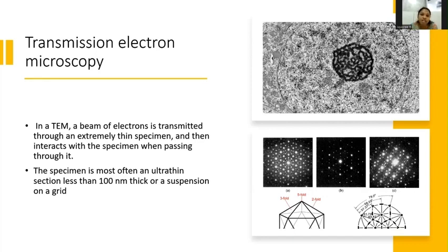Otherwise the electrons will get charged over the surface of the sample, and it may even destroy or damage your sample because of the heat which is generated on the surface of the sample. Okay, so whenever you are using a polymeric sample or this organic kind of sample in your electron microscopy, this high intensity electron beam can create heat on the surface of your sample.